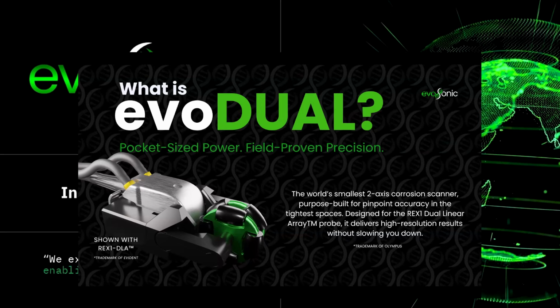As we paid attention to the tech scanning, we also found that the positional accuracy from tech to tech on the same spool of piping could improve. We started to see this was from relying on the technician as a human to maintain the probe's position over these index lines that they drew, thus adding more time to the inspection as the techs were going back and repeating scans to make sure the data was lining up to help those corrosion trends.